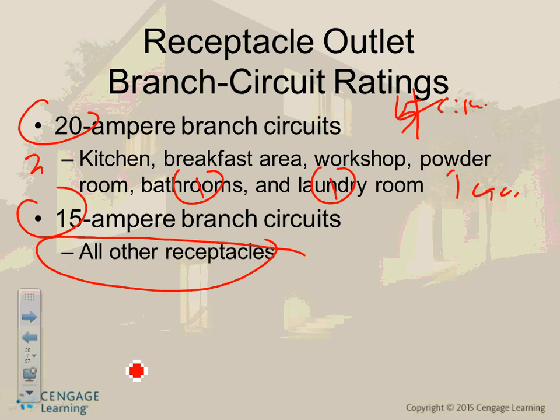Let's go over the circuits one more time. 20 amp circuits, where do I need them? Two in the kitchen, one in the laundry, one in the bathroom, four of them. I need a dedicated 15 amp circuit for the garage, or 20. I need a dedicated 15 amp circuit for the furnace, range, water heater, AC. These are all dedicated circuits with their own amps. Sump pump, dedicated circuit for the sump pump. Laundry 20.